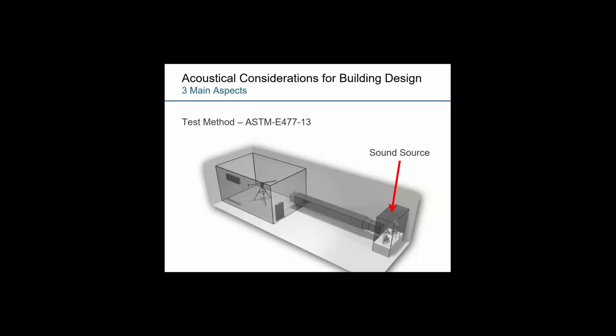The test method, comprised of a sound source, ductwork, and a reverberation room, is done in accordance with an ASTM standard, ASTM E477. And the way that the test is primarily conducted is that sound energy is created in the sound source and ducted and transmitted and then recorded and measured in the reverberation chamber. A silencer is then inserted into that system, and the test is redone under equivalent ideal conditions. The difference between the silenced and unsilenced measurements that are recorded and taken is the insertion loss. Effectively, the higher the insertion loss, the more sound is being taken out of that system by the silencer.